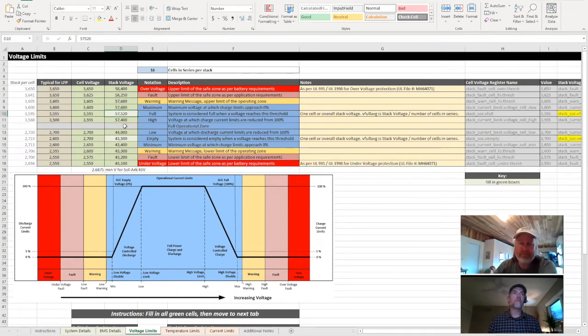So if we go to, let's say, 57.2 on the inverter, or 57.3, something like that, and charge up to there, I think that will be very full in the batteries. You're going to be very close to getting a fully charged battery, and you're only going to lose maybe a couple percent of SOC, which will be pretty minimal.